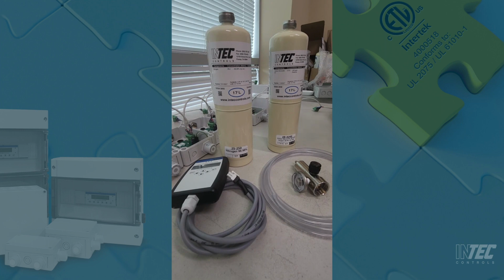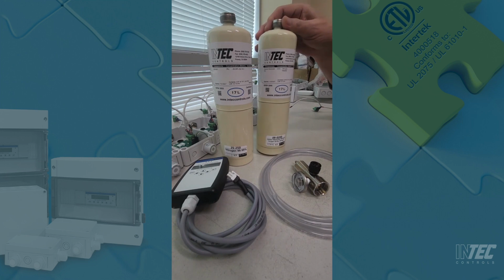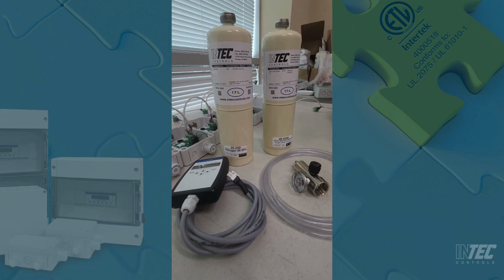And that is, you need a zero gas. Today we're using 99% pure nitrogen for our zero gas. For our calibration gas, the gas must be between 30 and 90% of the range of the sensor. Our range is 0 to 250. We're going to be using a 200 ppm carbon monoxide gas, which is 80% of the range.